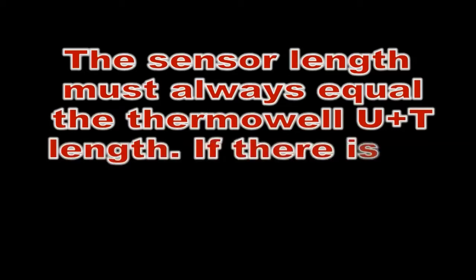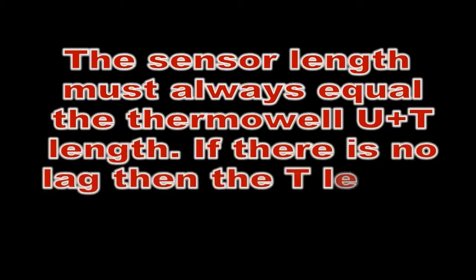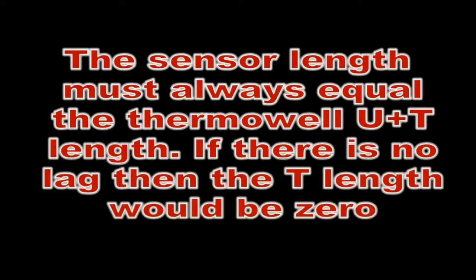Now that we have an understanding of the U insertion length and the T lagging length on a thermowell, the following rule always applies when selecting the sensor. The sensor length must always equal the thermowell U insertion length plus T lagging length. If there is no lag, then T will be equal to zero.